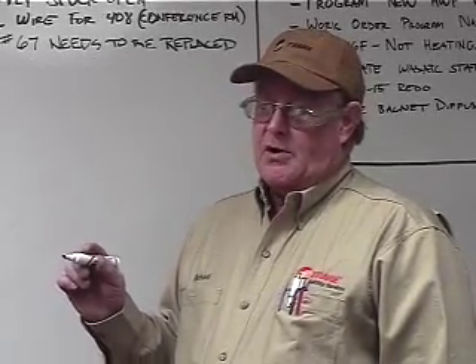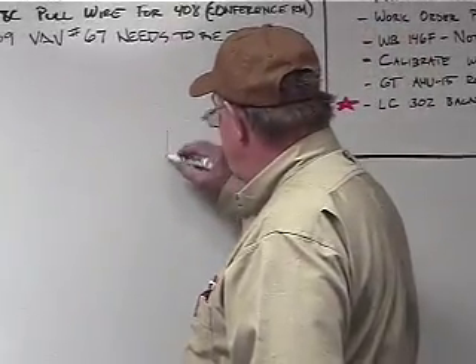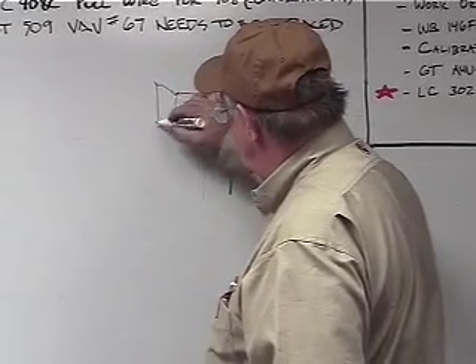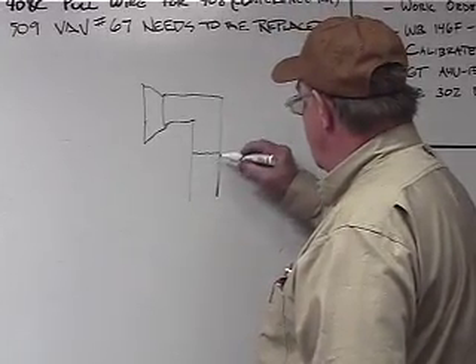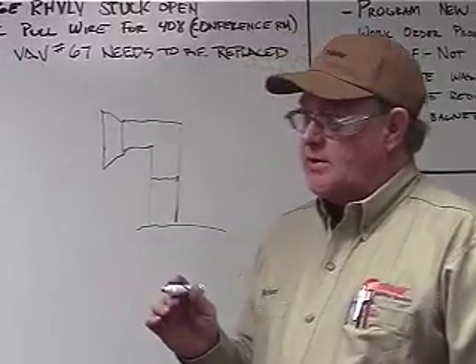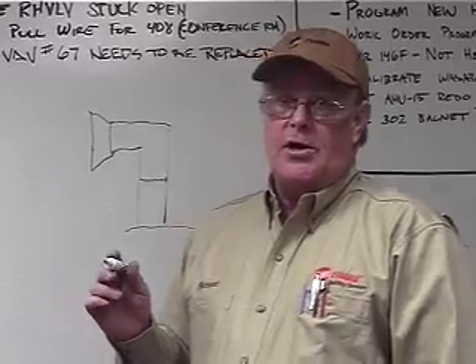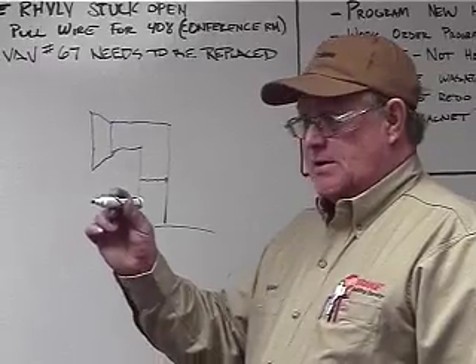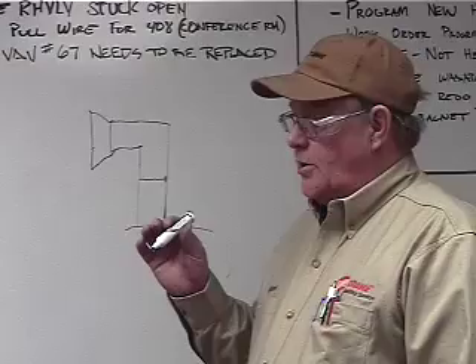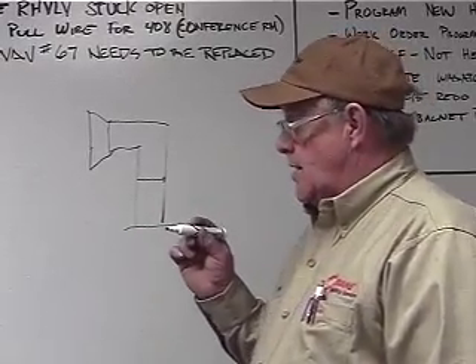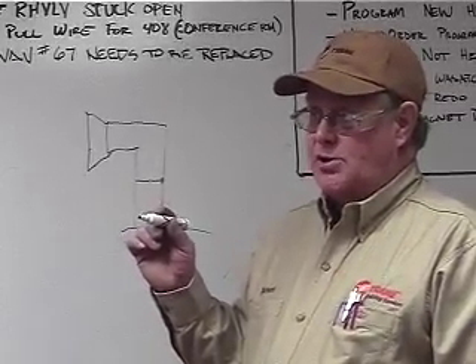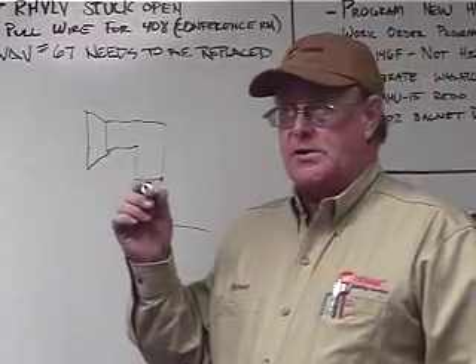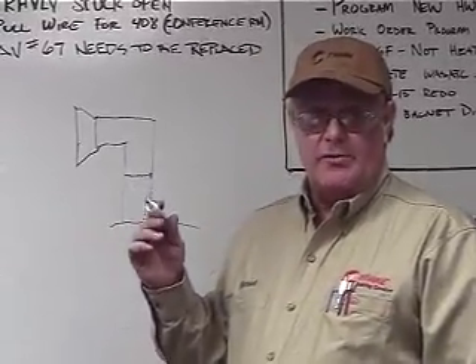The only other difference that there is on this chiller, we have what they call a flow gauge. You've got little meters up on the suction elbow. And it's situated about right here, or here's your evaporator. It's situated about right here, which is a set of gauges. Now these gauges are taking your inlet water pressure and your outlet water pressure on your evaporator and the condenser. And what it does is it takes and figures out calculations that'll give you tonnage on what your chiller is actually doing. And it'll also, if set up, can load and unload the chiller by capacity. I don't know how this one's actually set up, so I can't tell you for sure, but we can set it up either way.